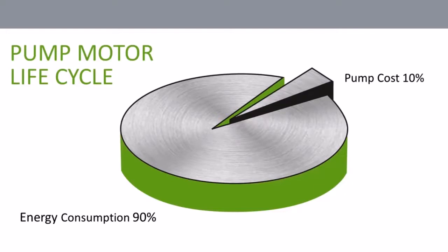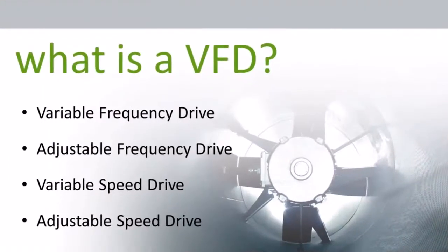Most motors are oversized to deal with the worst-case scenario, the peak load. A VFD allows you to run that motor at the load it needs to be, instead of running it at peak load all of the time. Another benefit is its built-in soft start capability. These two things alone are going to give you savings, not only on energy, but also by extending the life of the motor. So, what is a VFD?